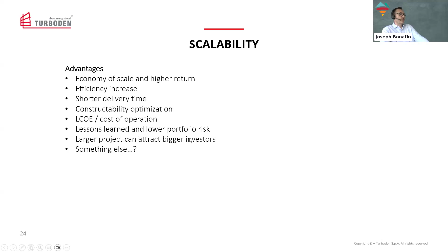Of course, you have challenges because there is higher risk capital initially required. There are some supply chain bottlenecks on specific items, long lead items like generators that have reached, for the 4-pole, probably the largest frames available. Then you have to go to 2-pole, but you need a faster turbine. So there is a sweet spot at around 100 megawatt capacity for a single 4-pole generator.